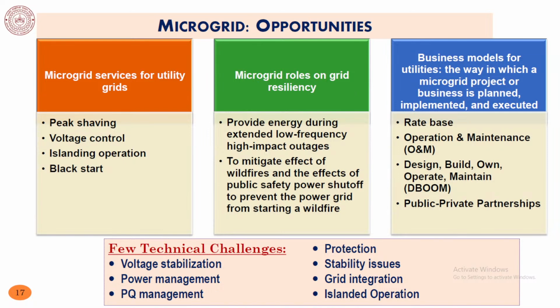In fact, in 2012 when we investigated, we found that on 30th July restoration of electricity took 14 hours. On the next day, 31st, because they had learned a little bit, it took 8 hours. One main reason was that no pocket was having electricity to black start the generators. So if you have microgrids, a few pockets will always be there. There were very few pockets which had electricity, so they could, with a lot of difficulty, restart. Whereas if you have microgrids at community level or strategic locations, you can take the electricity and restart the grid. So it offers a very great advantage there.